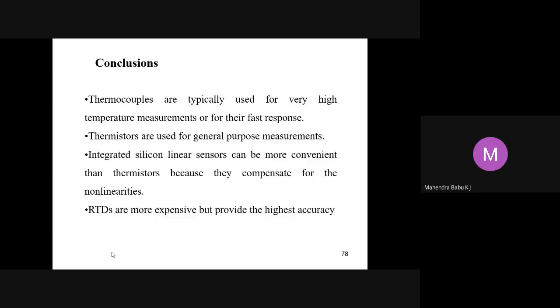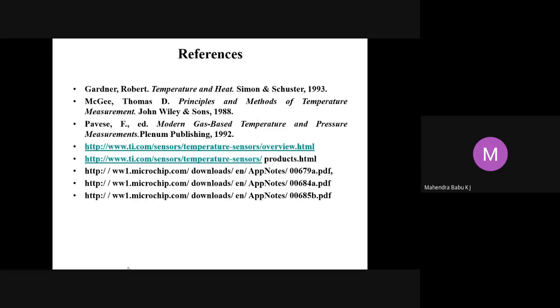And to conclude this session, thermocouples are typically used for very high temperature measurement or for their fast response, and thermistors are used for general purpose measurement. Integrated silicon linear sensors can be more convenient than a thermistor because they compensate for non-linearity. RTDs are more expensive but provide the highest accuracy. These are some of the references which I have used.